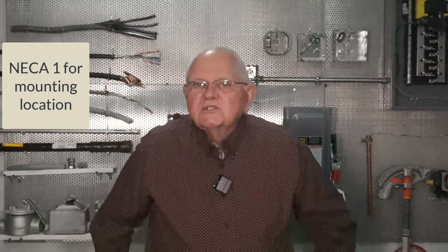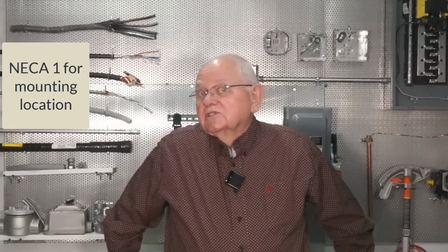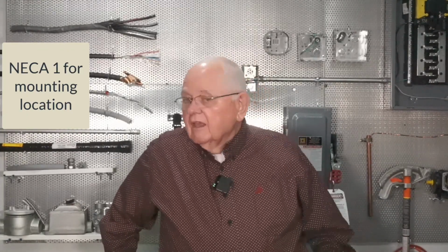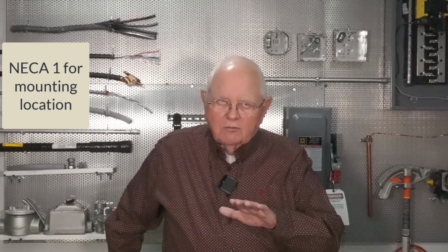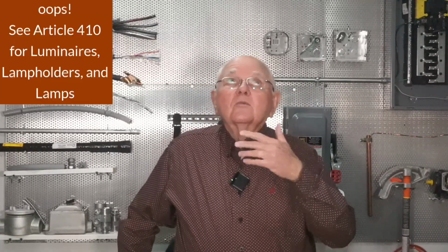Kitchen, utility room receptacles, we should be mounting those 42 inches off the floor from the center of the box to our floor level and 6 inches above countertops and whatnot. Follow your specifications, follow your local jurisdictional requirements, best industry practices, and so forth. These are the NECA 1 requirements. I could take all this information we're talking about and go back to what? NEC Article 406 is on receptacles and cord connectors and attachment plugs. And I could take a look in Article 410 on luminaires and lighting.